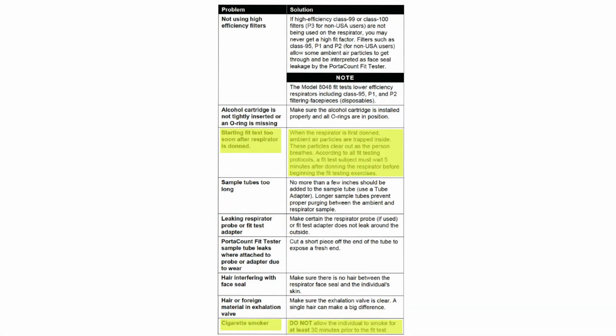A particle purge time is required to allow someone in an ambient aerosol instrument to get in the mask, have the filter, be connected up to a machine, or have some way of blocking the port off to purge the mask of particles, which takes breathing and time. Yep. OSHA requires a 5-minute time. It's in the user manuals that you see on your screen. So that's a pivotal and important part, to purge the mask of particles to make sure that you're ready before you start a fit test. And that's part of the requirements to operate the machines the right way. So it's a big environmental requirement as we see it in fit testing.